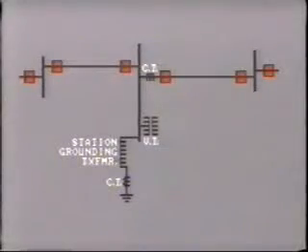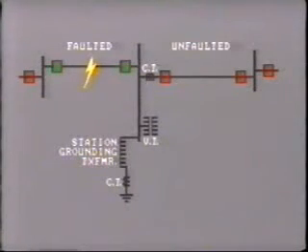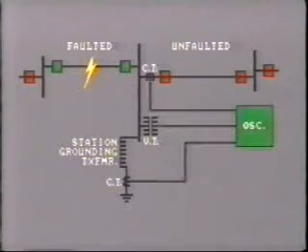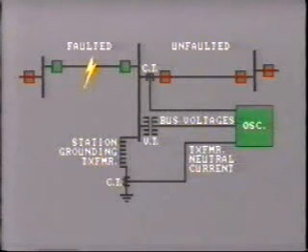Now let's consider case 1, an unsuccessful line reclosure. In practice, this happens quite frequently when the line does not stay de-energized long enough for a temporary fault to clear on its own. In this example, the oscillograph has captured the substation bus voltages in all three phases, the transformer neutral current and line current for one of the transmission lines.